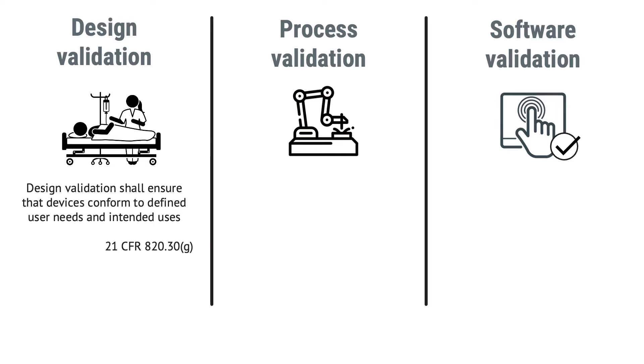There are at least three different types of validation: design validation, process validation, and validation of computer software. Design validation shall ensure that devices conform to defined user needs and intended uses. For example, if you design software that you claim will help elderly patients monitor their blood pressure, you would be doing some user tests with representative users to see that they understand how to use the software. Design validation is often done in a real or simulated environment.